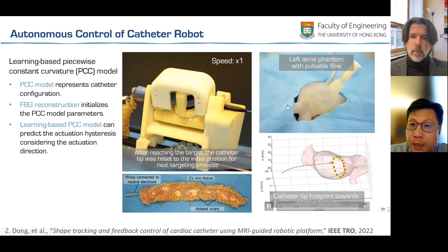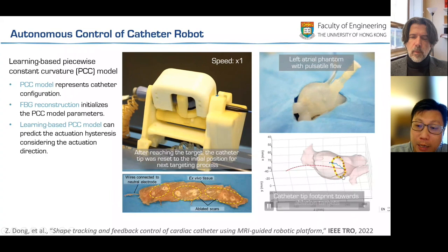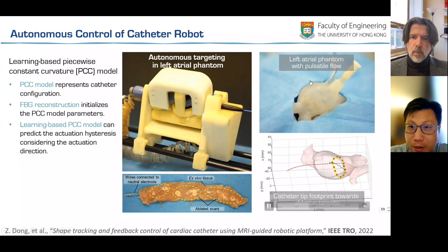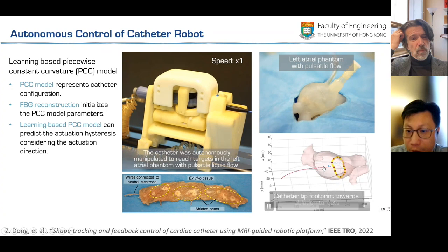Here we did a test to see how the robotics, how the catheter tip can be navigated inside the rubber left atrium. We simulated the pulsatile flow into that left atrium phantom so we can see the tip is actually adversely affected, deviating from the target.